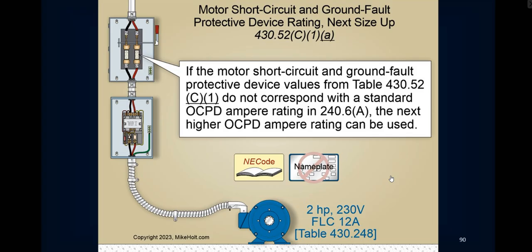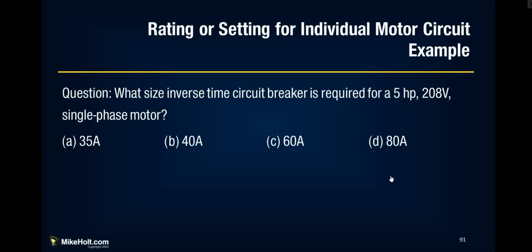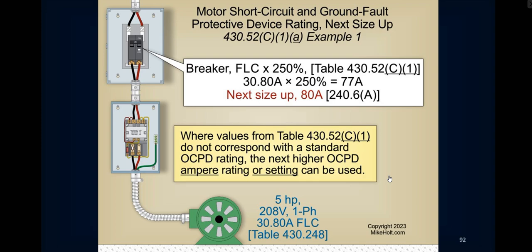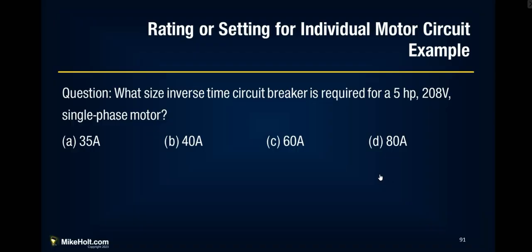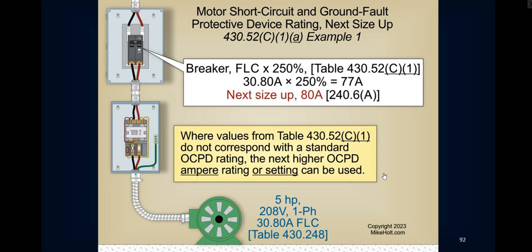Okay. A couple more slides and I'm almost done. What size inverse time circuit breaker is required for a 5 horsepower 208 volt single phase motor? So the breaker would be FLC times 250%. And that was an inverse time circuit breaker, I believe it was. Yeah.